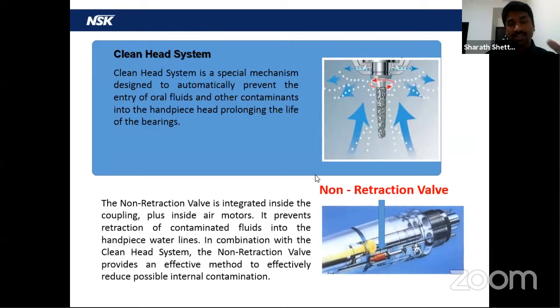This non-retraction valve is installed in the coupling of the handpiece, not on the actual handpiece. That means whichever doctor is not using a coupling type of handpiece, that handpiece does not have protection against this reverse flow into the water line. This non-retraction valve, as you can see in the picture, is the small red part on the screen, but actually it's white in color. This prevents the reverse flow of water.